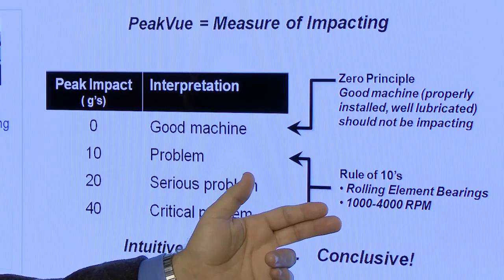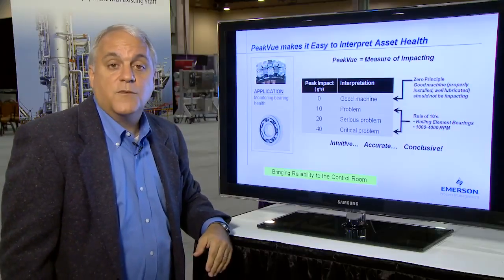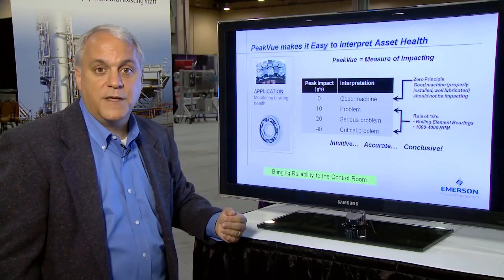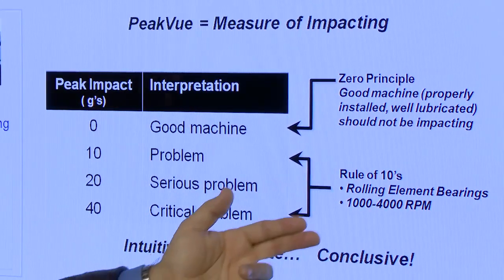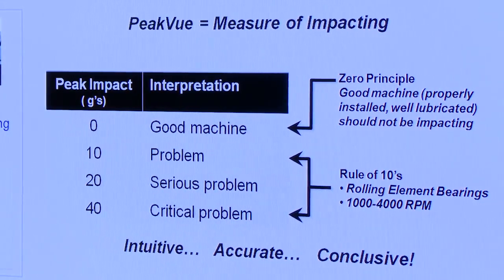The second principle applied when monitoring PeakVue is referred to as the rule of tens. The rule of tens applies for rolling element bearing machines operating between 1,000 and 4,000 RPM. It simply states: when the PeakVue levels reach 10, there is some problem developing on the machine; when they double to 20, there is a serious problem; and when they double again to 40, there is a critical problem on the machine.